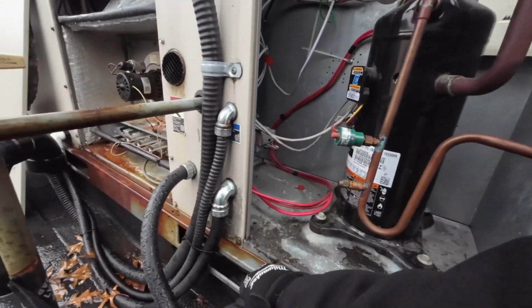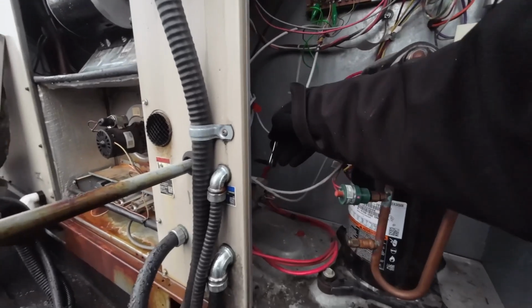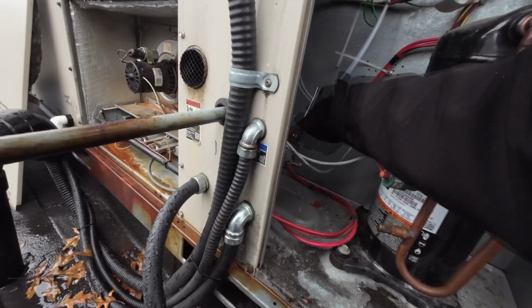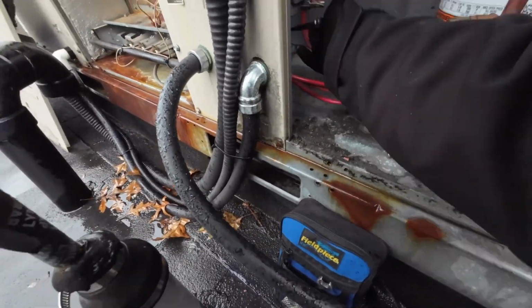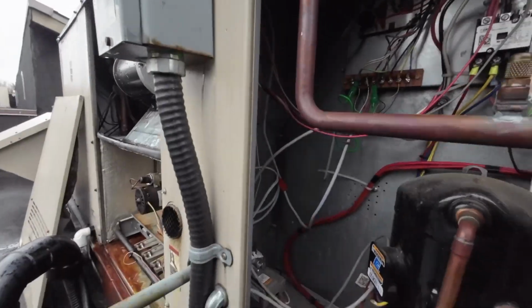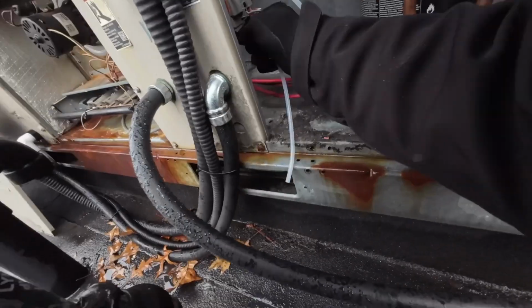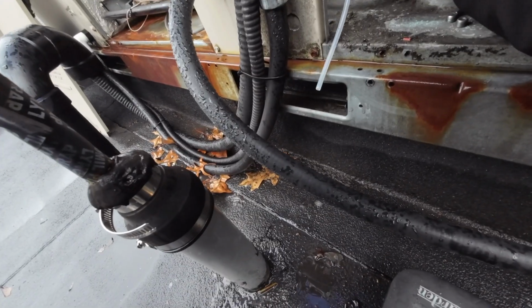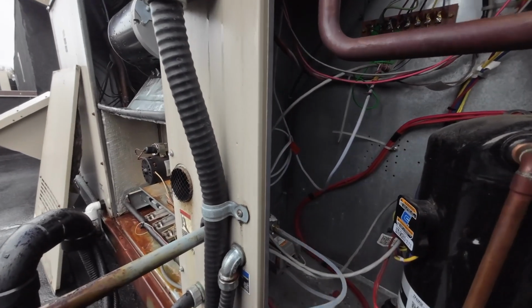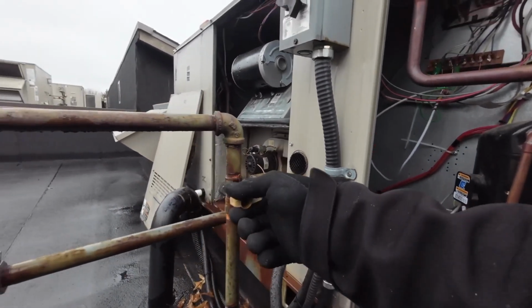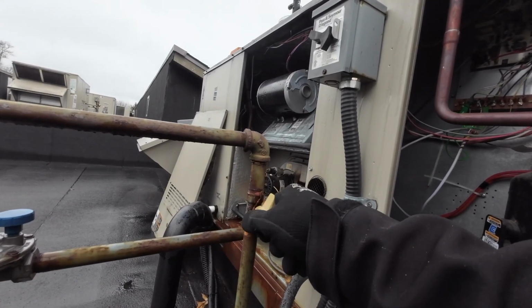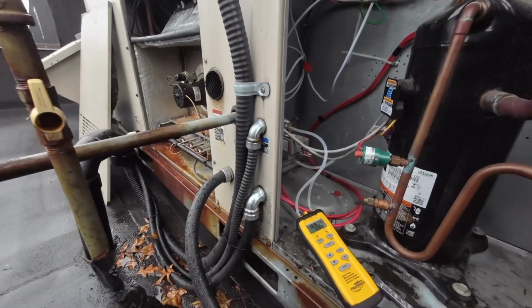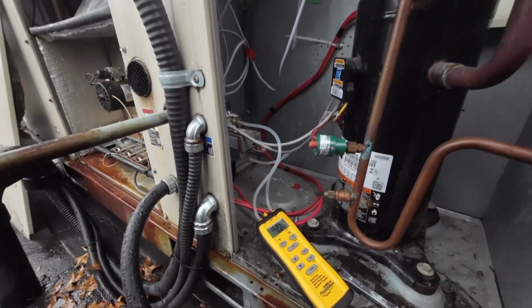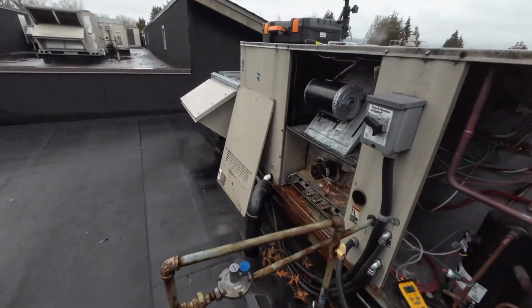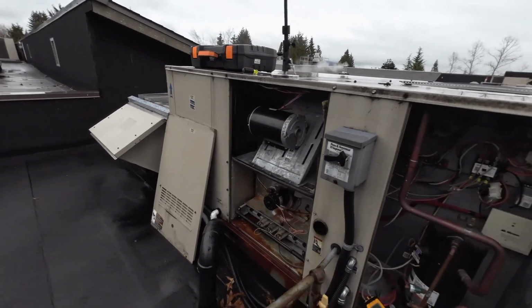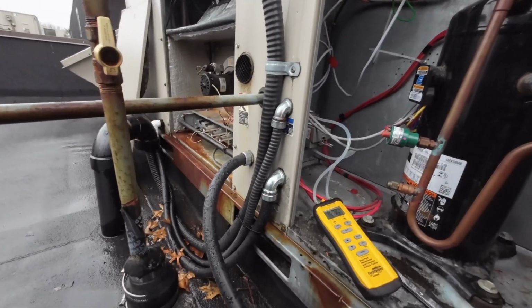Check it out. I saw this a few years ago, these service wrenches for gas, just the smartest thing ever. Open this nice and slow so we don't end up damaging this regulator. So we've got a standing pressure of 16.92 inches of water column. Alright, so let's turn it on and see what goes on here. That was just the standing. Let's see what it drops down to.